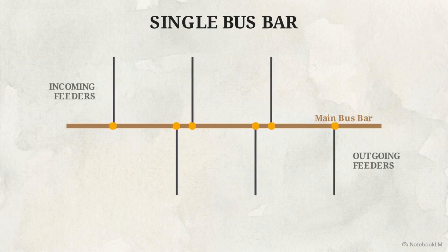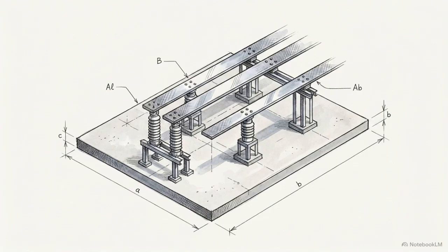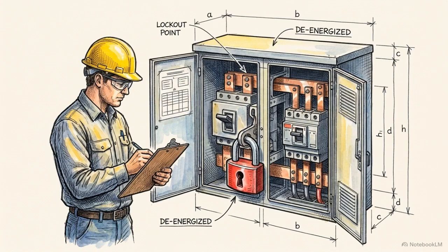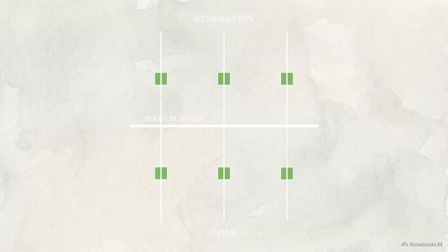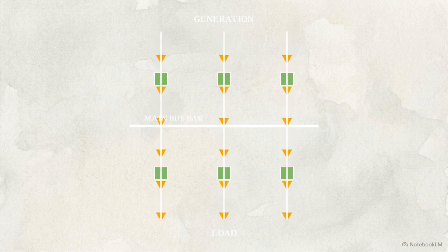The evolutionary process starts with the simplest possible topology, the single busbar scheme. Its primary advantages are immediate. It has a low initial cost, it is extremely simple to construct, and it is easy to maintain in locations where temporary network shutdowns are acceptable. Under normal conditions, current flows from generation feeders, merges on the main bus, and exits to the load.